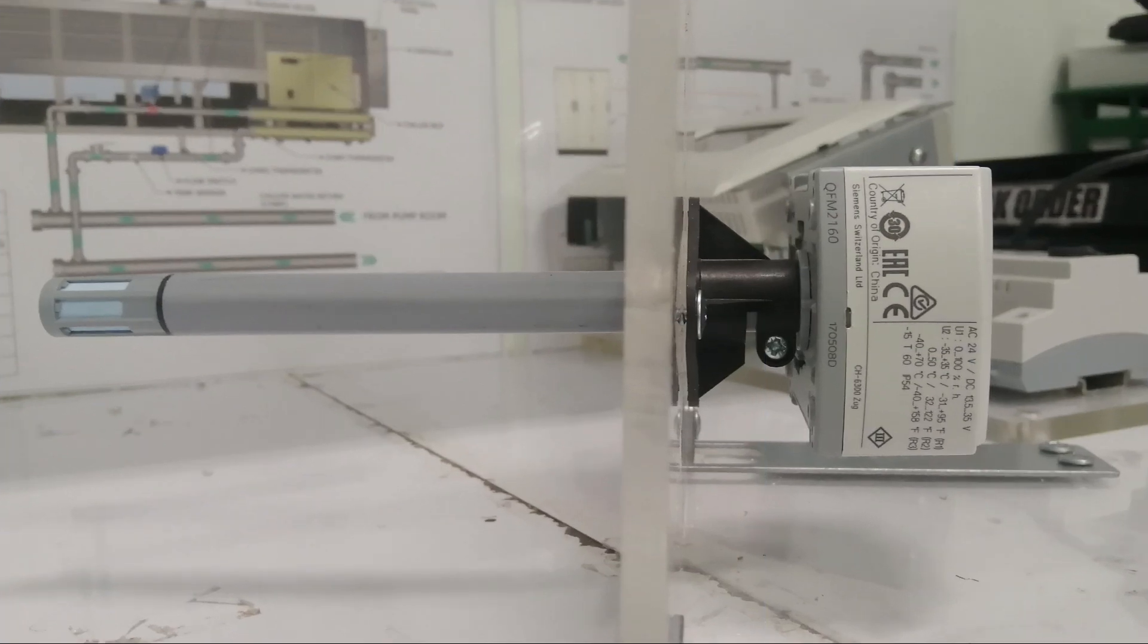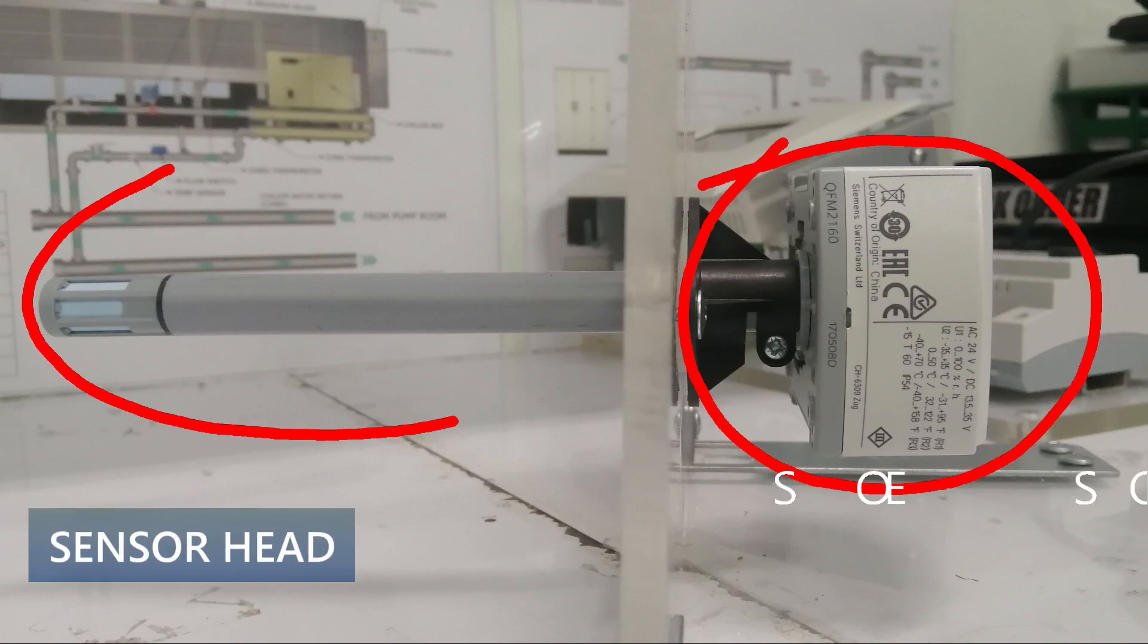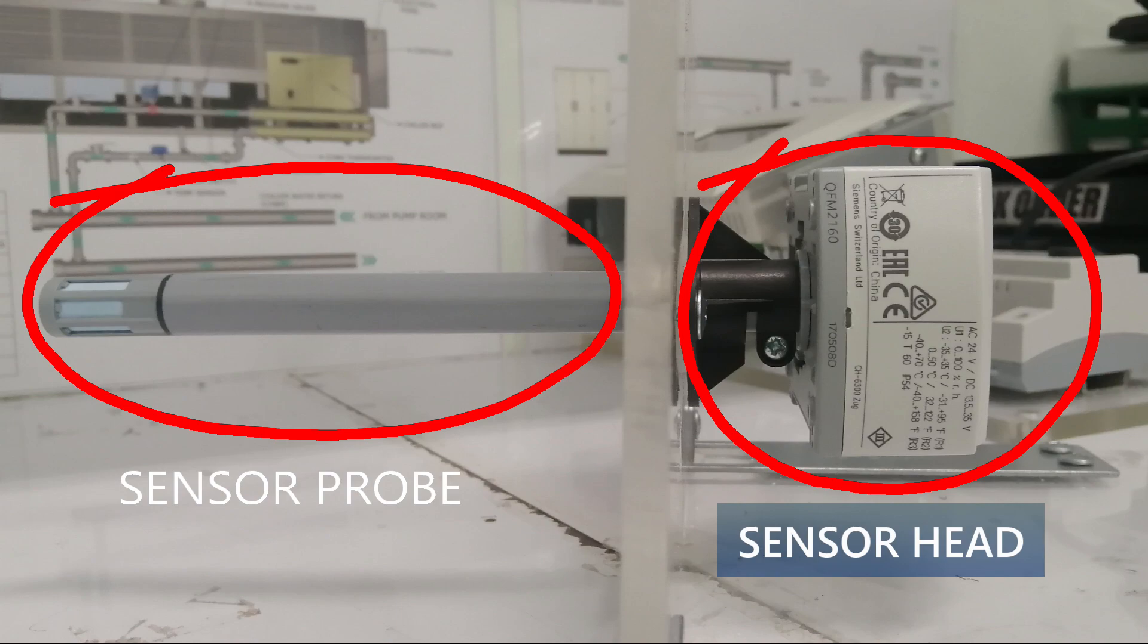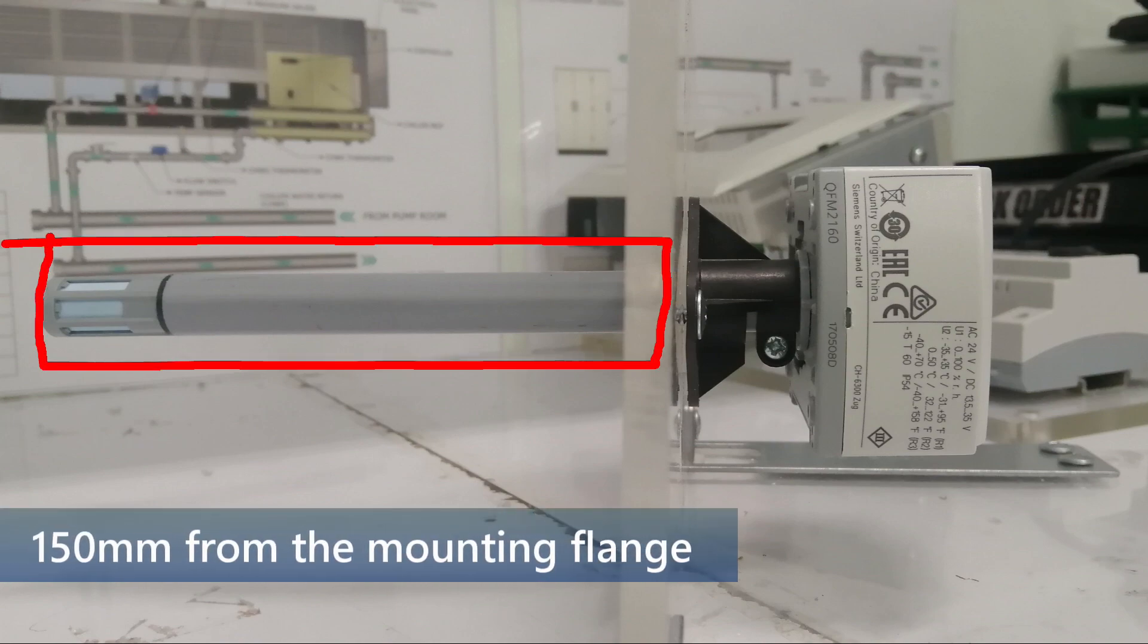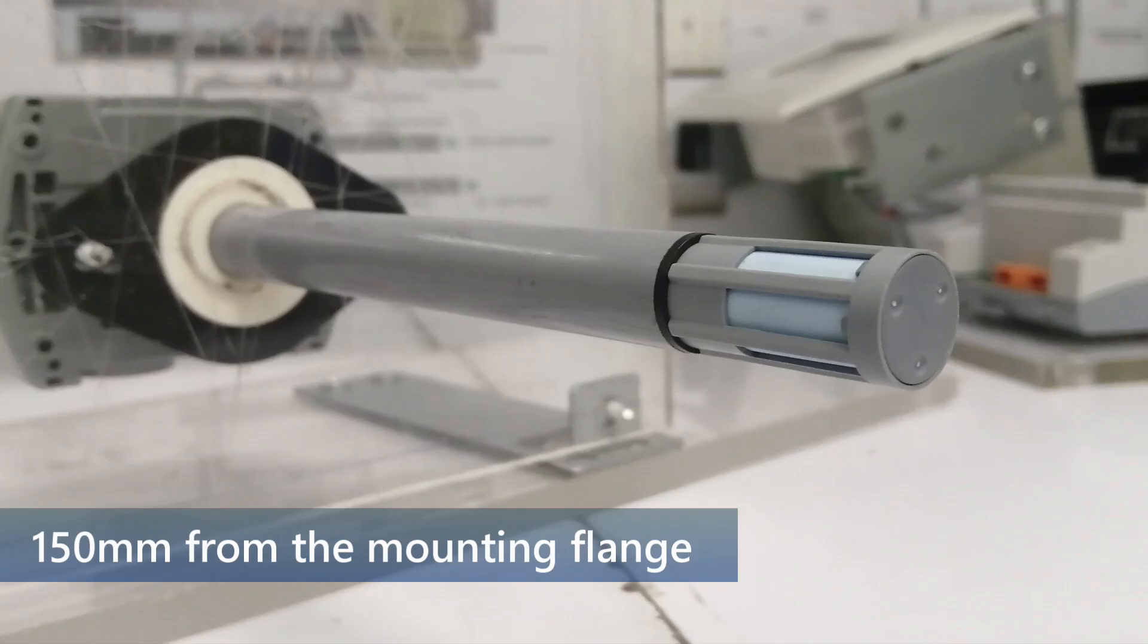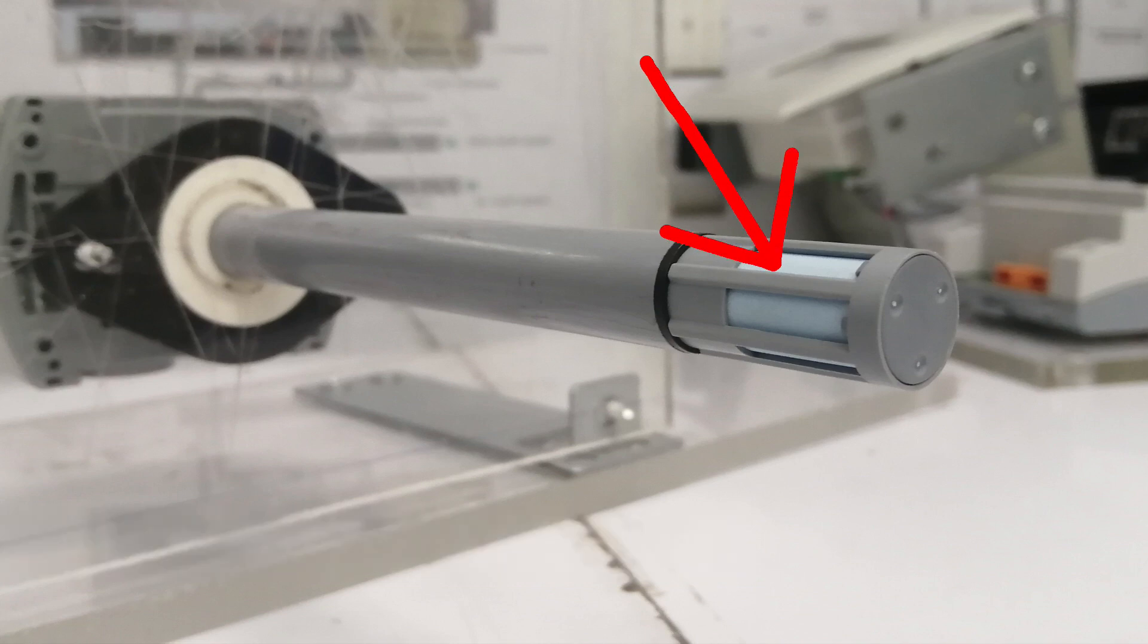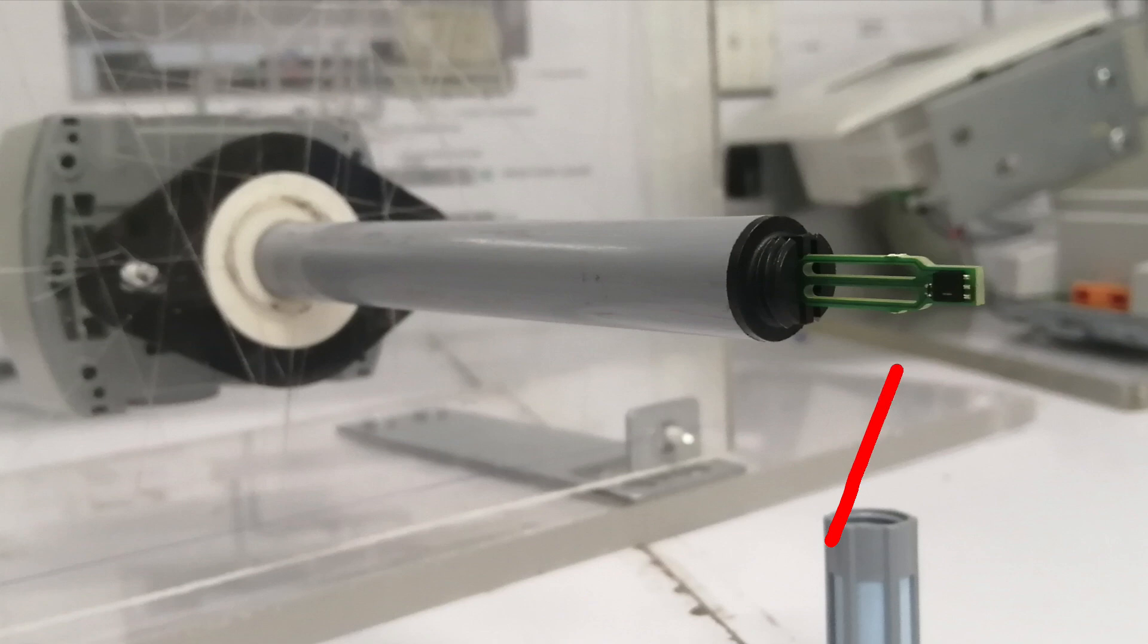This is Siemens QFM3160. There are two sections: the sensor head and the probe. Sensor probe length is approximately 150 millimeter from the mounting flange. At the end of the probe there is a filter cap. Inside this filter cap is where the sensing element is located.